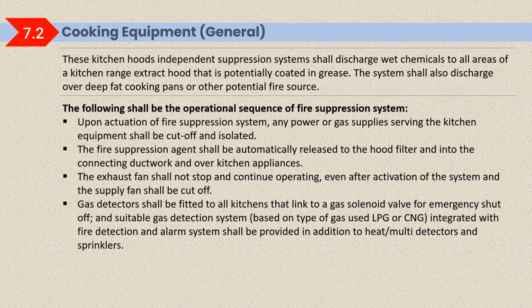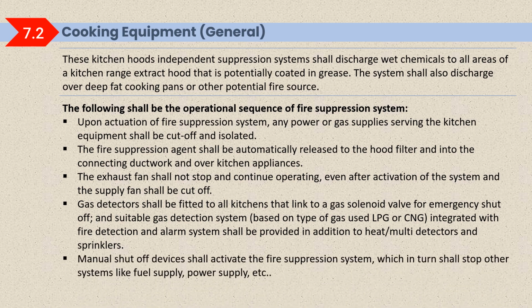A gas detector shall be fitted in all kitchens and linked to a gas solenoid valve for emergency shut off. A suitable gas detection system based on the type of gas, that is LPG or CNG, integrated with the fire detection and alarm system shall be provided in addition to heat multi detector and sprinkler.